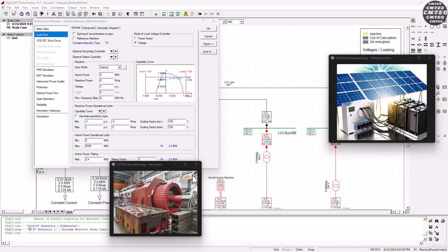This means you cannot produce active power rated above the capability of your prime mover, basically the mechanical power that's coming through your generator. All of these conditions combined form the classic curve of the generator capability envelope.